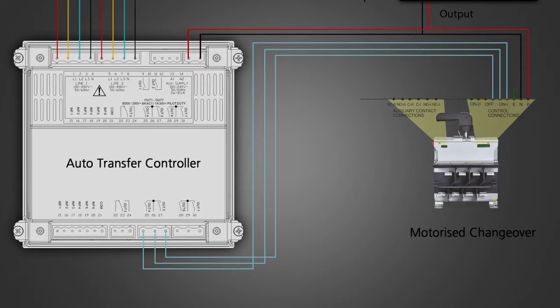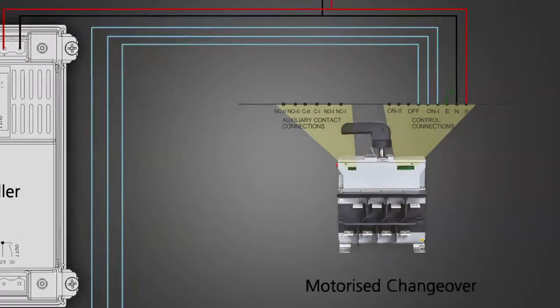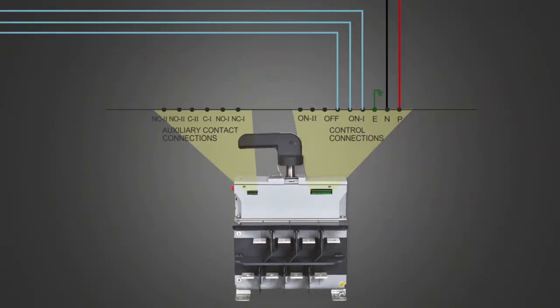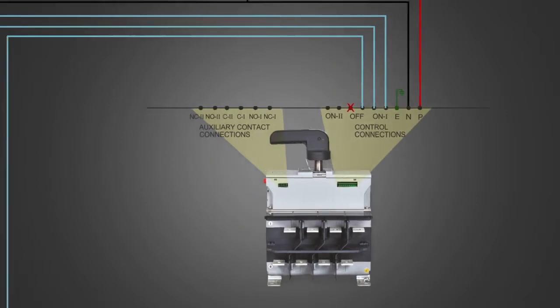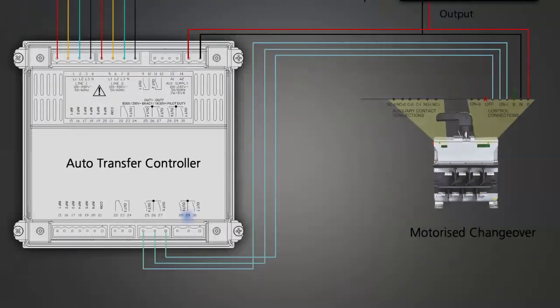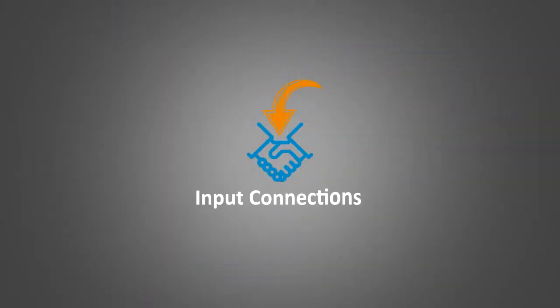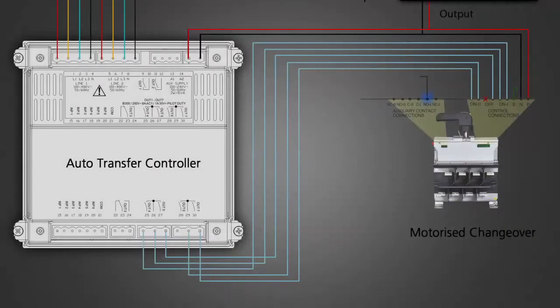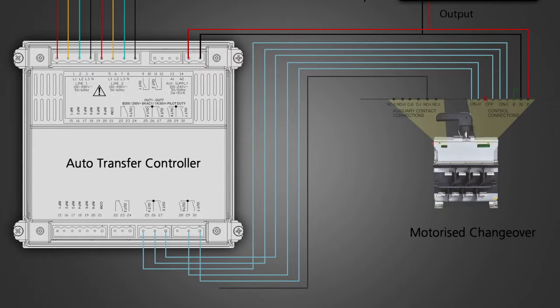Caution: no connection is required for pin 1 of the off position. Terminals 29 and 30 of output 7 of the controller connected to MCO position 2. Input connection from MCO auxiliary contacts is connected to the input terminals of the controller as shown.